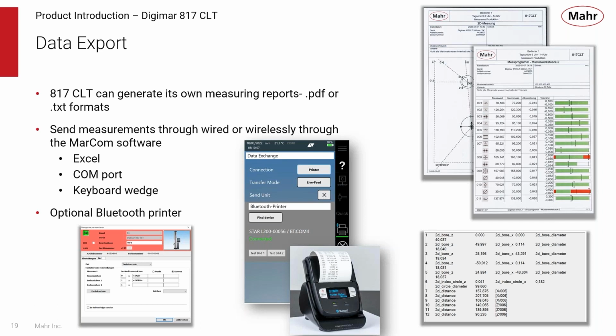Individual readings can be sent either through a wired connection or wirelessly through the Marcom software, allowing you to send individual data points directly to a computer. Marcom software is completely free and can be downloaded from the Mahr site at www.mahr.com/Marcom. It will very quickly and easily pass off measuring data from the 817 CLT to an Excel spreadsheet, to third-party software via a COM port, or via a keyboard wedge style emulator.